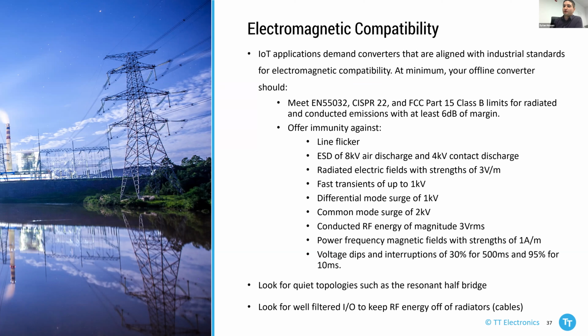From an immunity standpoint, we don't want electromagnetic energy to take our converters offline. The basic requirements against 61000 level testing call for ESD immunity of 8 kilovolts air discharge and 4 kilovolts contact discharge. In all honesty, with a power converter that's pretty easy to accomplish because of all that bulk capacitance. ESD doesn't really stand much of a chance of hurting most of these converters.